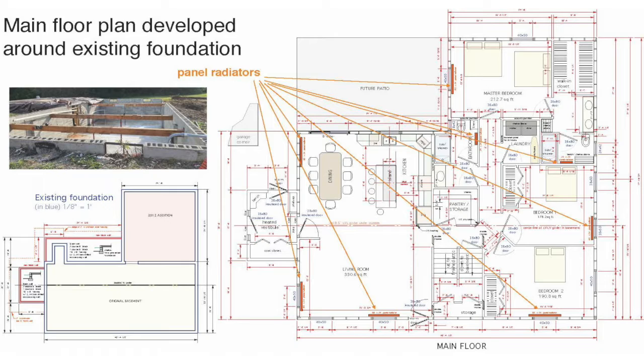Floor plan, again, it was quite a bit of space here. It was a big open area, kitchen, dining area, living room, a couple bedrooms here, master bedroom back here. And keep in mind, we had to design this around an existing foundation. It's not like we could make major changes in the foundation. And right now it's actually 5 bedrooms, 3 full bathrooms, and the design load is about 35 or 36,000 BTUs per hour, and that's at -5 Fahrenheit outside.